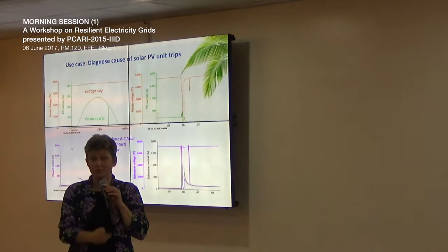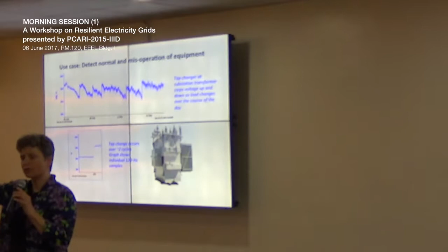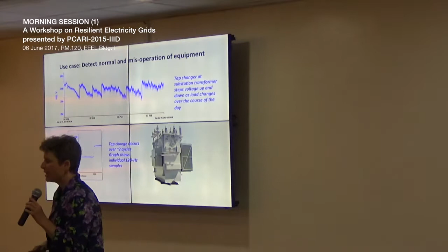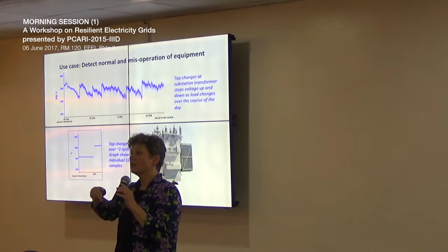Another example of phenomena that weren't really easily visible until now are voltage tap change operations. These are electromechanical pieces of equipment at transformers that effectively change the turns ratio by changing the mechanical connection point of the wires. They have to adjust voltage because depending on customer load, more load and current means more voltage drop down the line, so you have to compensate. These tap change operations were never really a big deal, except now as we begin to see more solar generation on these circuits.